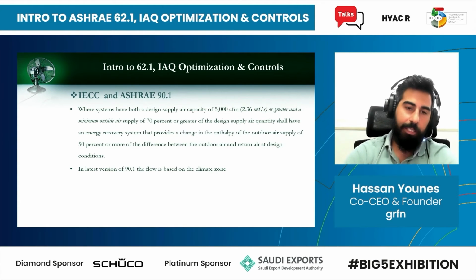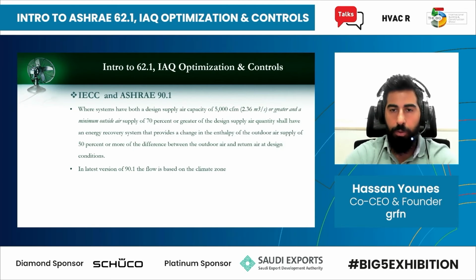Based on that, the standard prescribes when you need to have outside air heat recovery. The 5000 CFM threshold is still in, let's say, the Dubai Green Building codes or regulations. But if you look at the latest 90.1, it depends on the climate zone. You can see that for a place like Dubai, if you have a total outdoor air handling unit, the quantity where you need to add heat recovery is much less than the 5,000 specified in this standard.